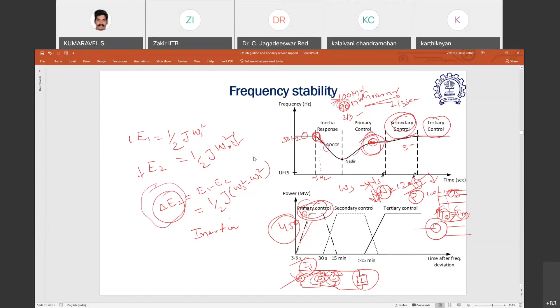Then comes tertiary control, which is a slow controller. It has primarily only one function here, which is to release the secondary reserve and maintain the frequency at the same value. That is how frequency control and the corresponding reserves come into the picture when you are controlling the frequency of the grid. We call this primary frequency control, and the corresponding active power reserve is known as primary frequency reserve. Secondary frequency control, the corresponding active power reserve is secondary frequency reserve. Tertiary control, the corresponding active power reserve is known as tertiary reserve.